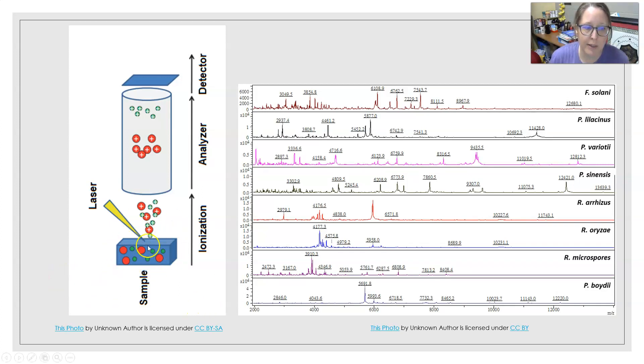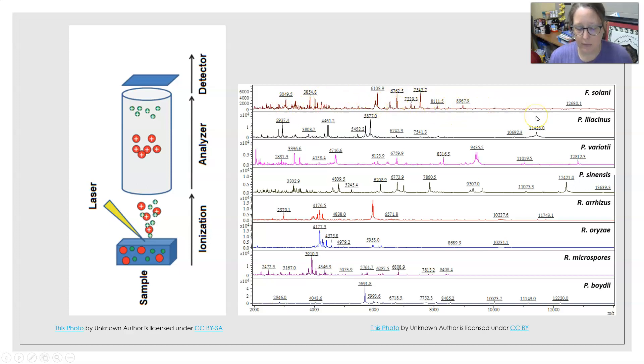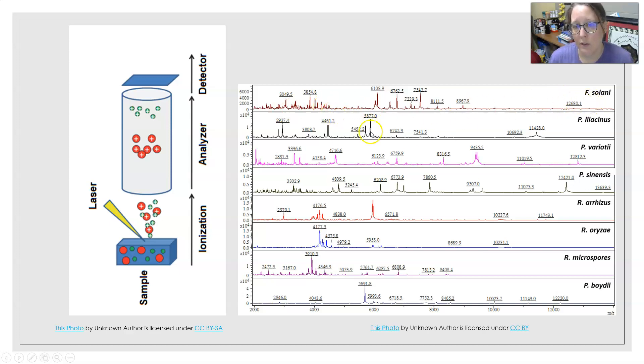This graphic illustrates the process: the MALDI ionization step is shown first, followed by entry into the Time of Flight analyzer, where smaller and lighter molecules reach the detector faster while larger and heavier molecules travel slower. This produces the peptide mass fingerprint mass spectrum, which is unique for each different type of microorganism, and the computer matches it up.